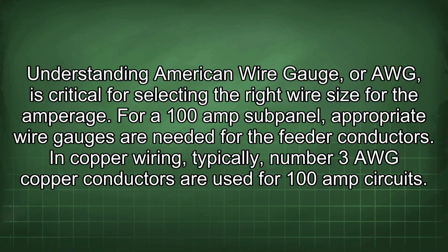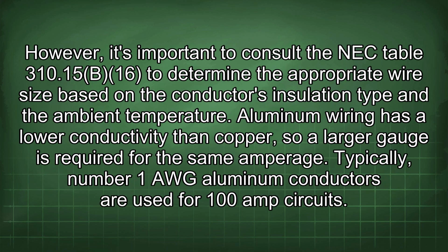For a 100 amp subpanel, appropriate wire gauges are needed for the feeder conductors. In copper wiring, typically, number 3 AWG copper conductors are used for 100 amp circuits. However, it's important to consult the NEC table 310.15(B)(16) to determine the appropriate wire size based on the conductor's insulation type and the ambient temperature.